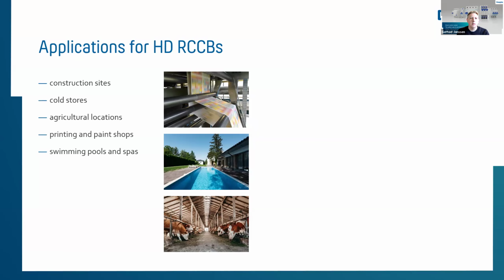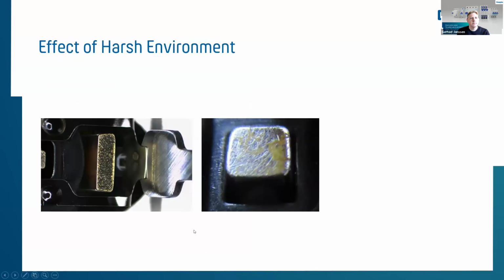This is also part of showing where the HD version is different from a standard type. This is part of the contact apparatus. This is one of the 4 main contacts, and it's made of special material, special plated material, which is more resistant against corrosion.